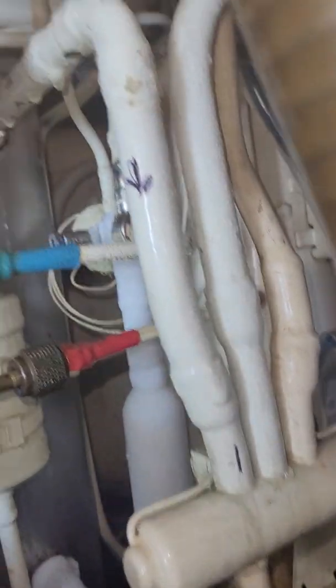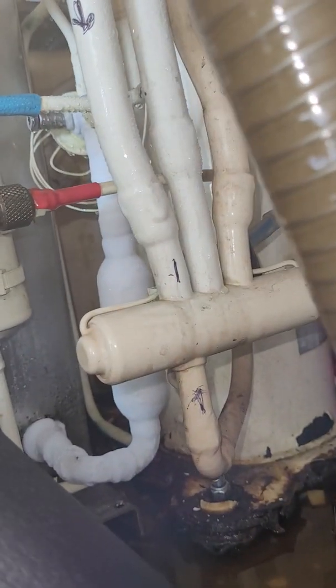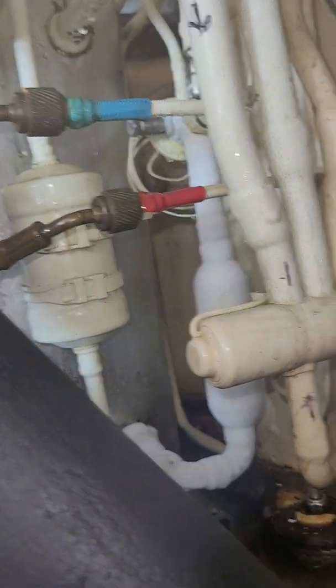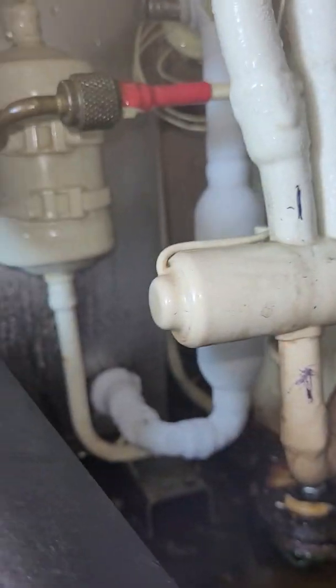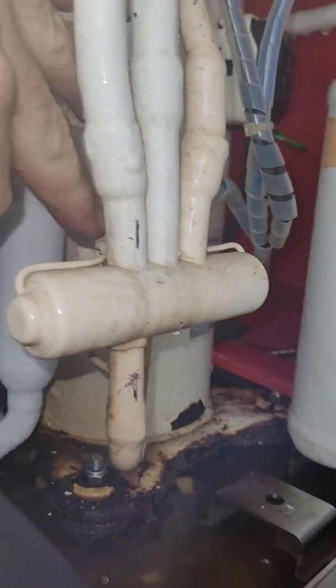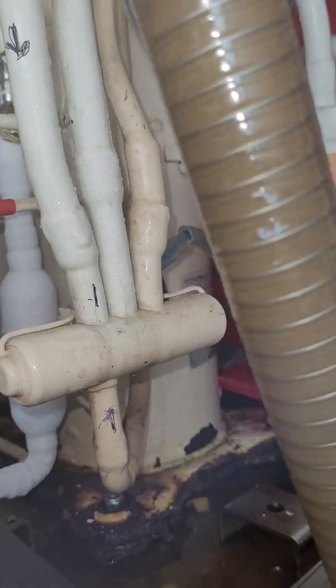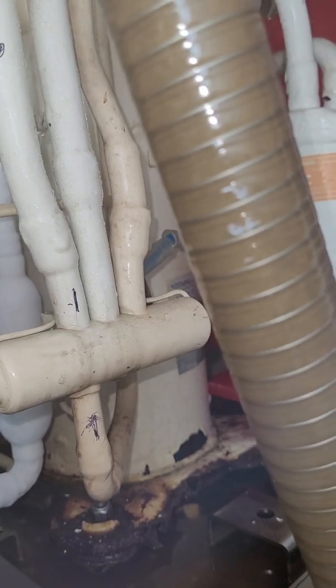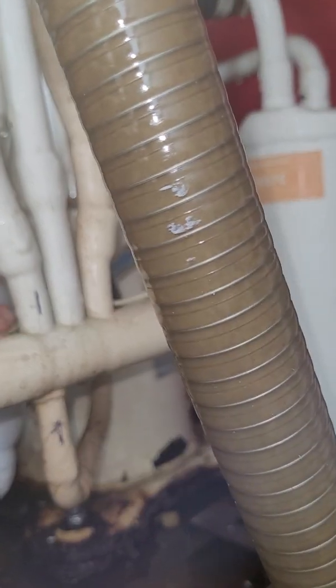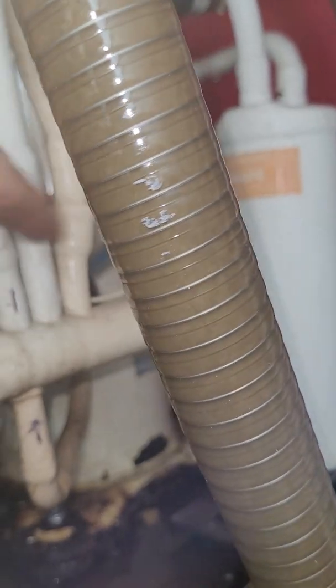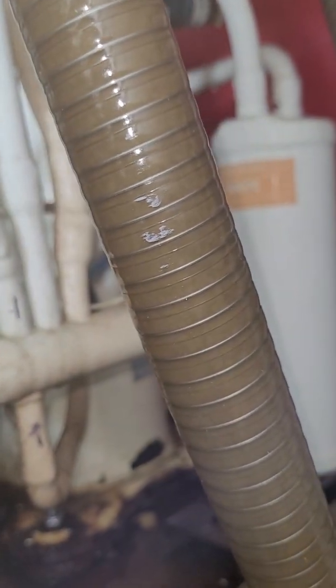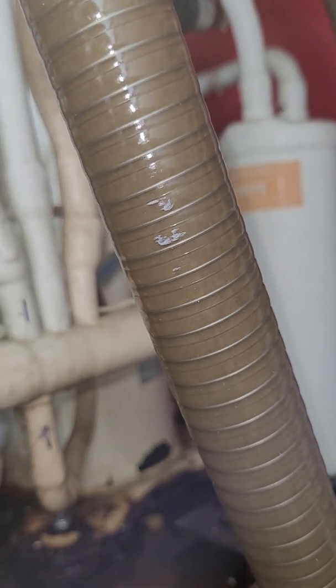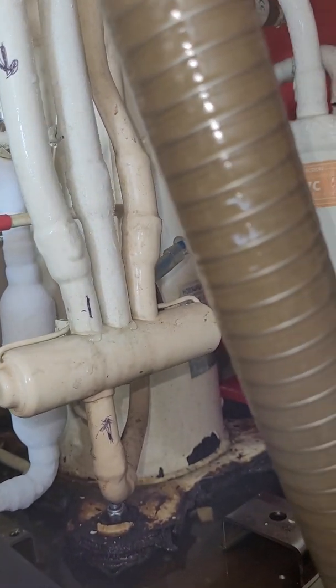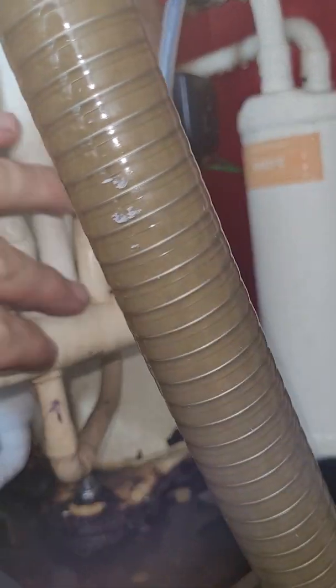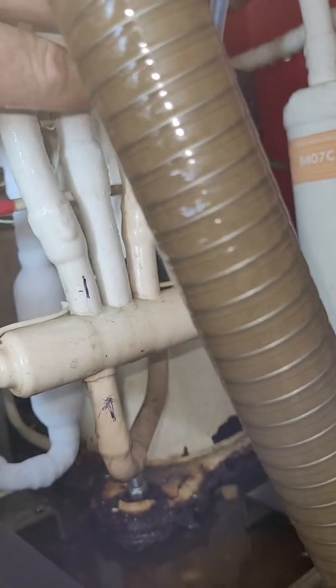The temperature of the compressor is quite alright, and what we're looking at also is the superheat. The superheat is kind of the opposite of the subcool. So what we have here, you can see the gas comes in, and this is a reversing valve, so you can actually use the system as a heating as well. It's a gas operated reversing valve, so it's a little electric solenoid which then uses the pressure of the refrigerant to reverse the system and run the refrigerant the other way around. So you can use this as a heating instead of a cooling. Now we're using it as a cooling. So gotta make sure that this valve is in the right position, which it is. You can feel it here on the pipes.